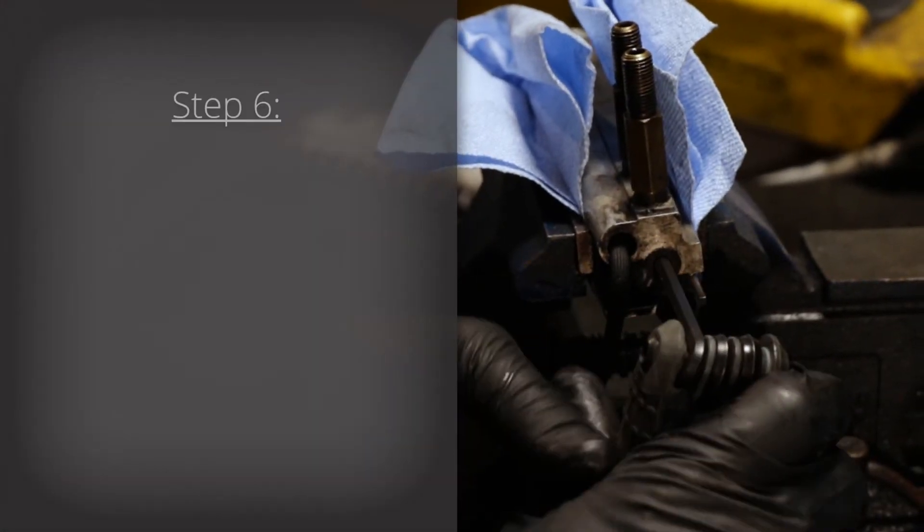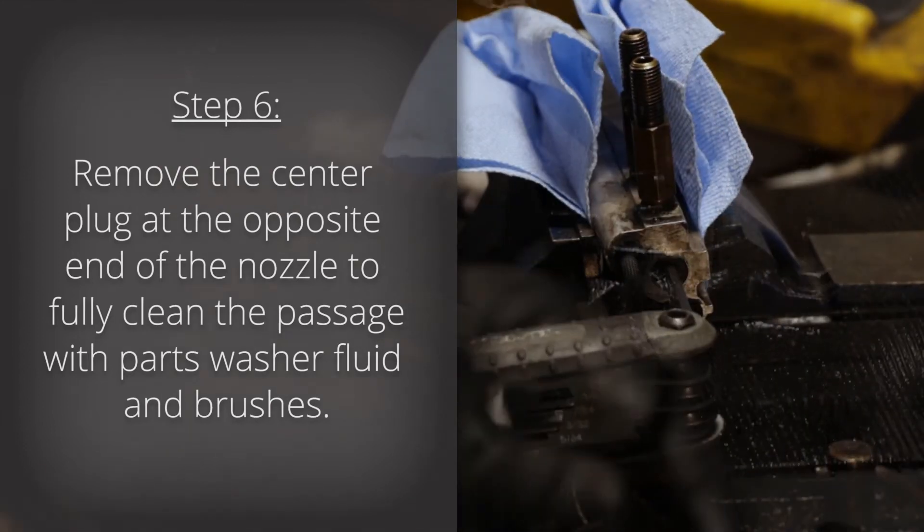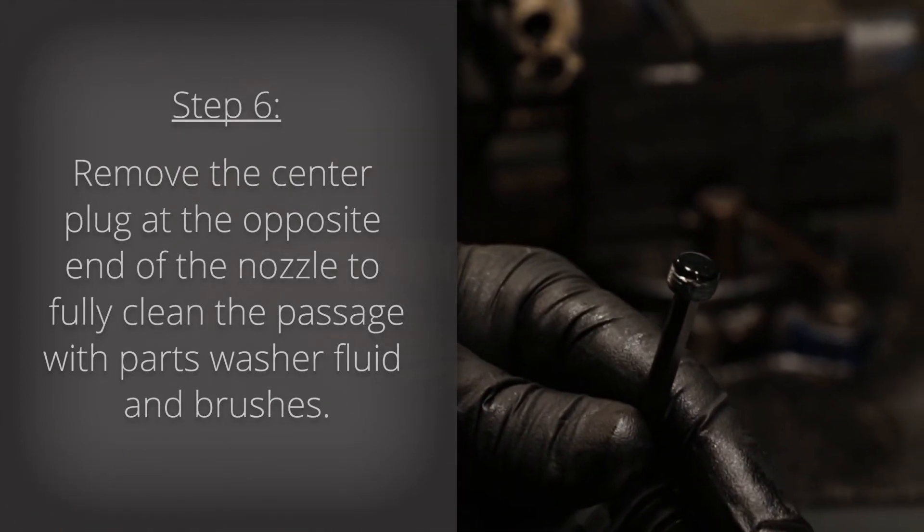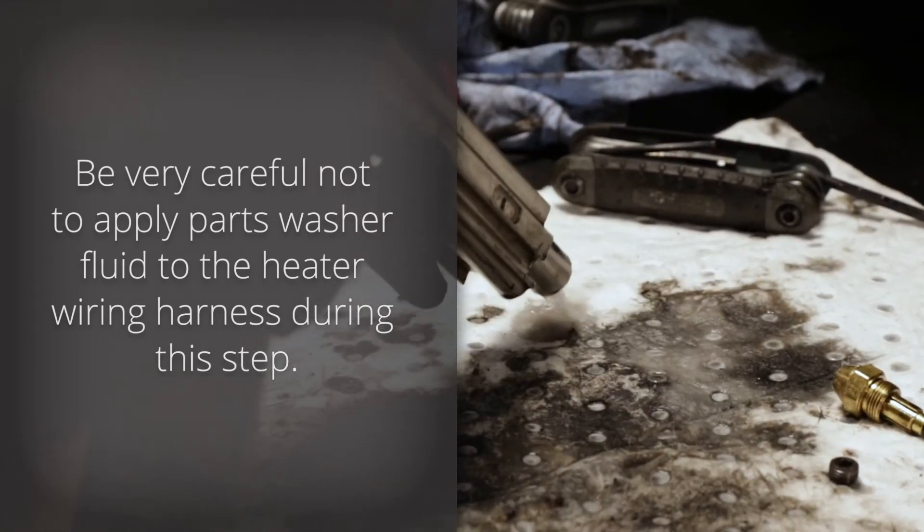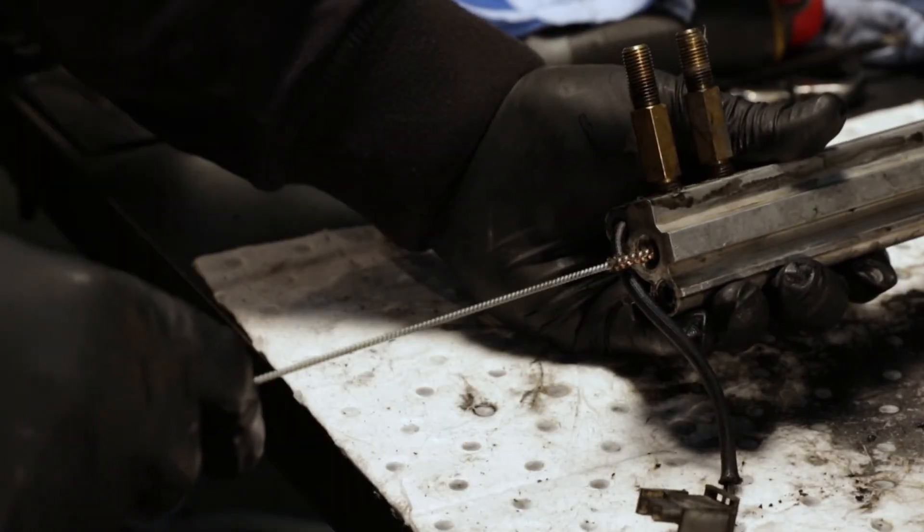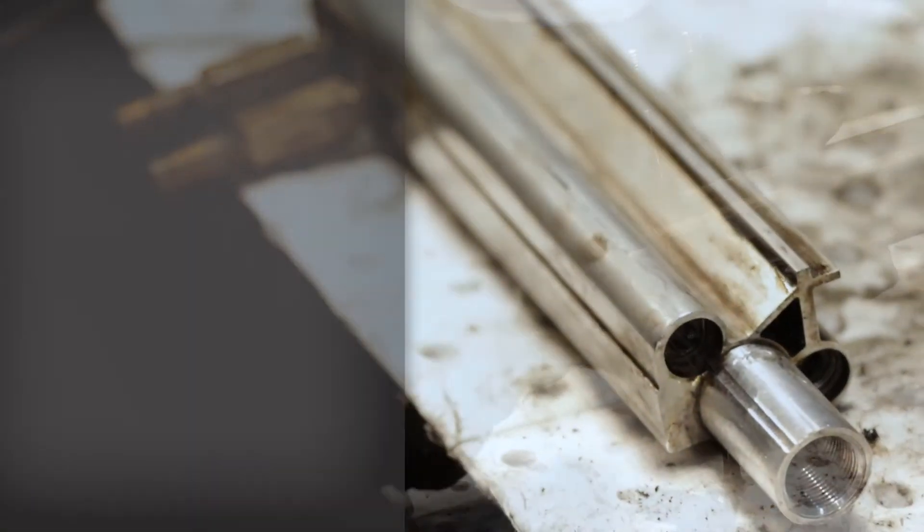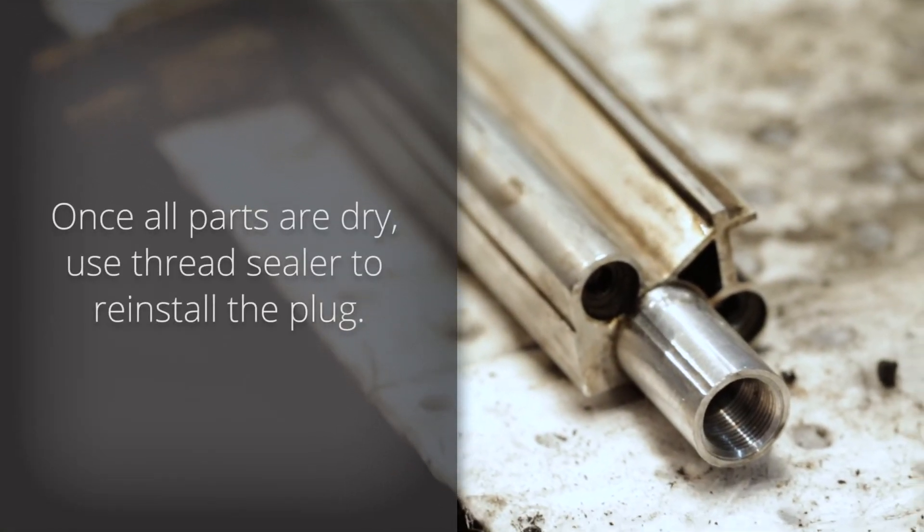Step 6. Remove the center plug at the opposite end of the nozzle to fully clean the passage with parts washer fluid and brushes. Be careful not to apply parts washer fluid to the heater wiring harness during this step. Once all parts are dry, use thread sealer to reinstall the plug.